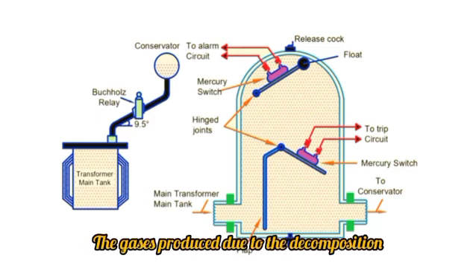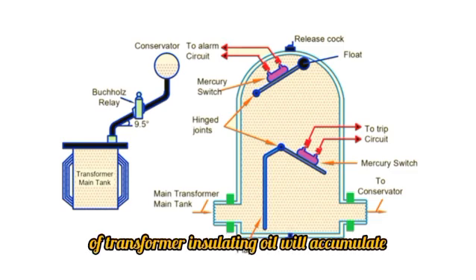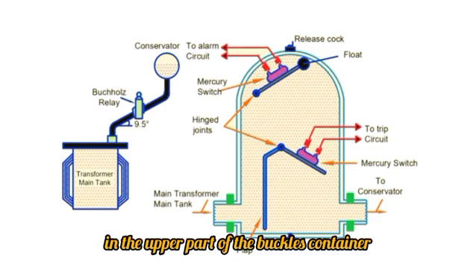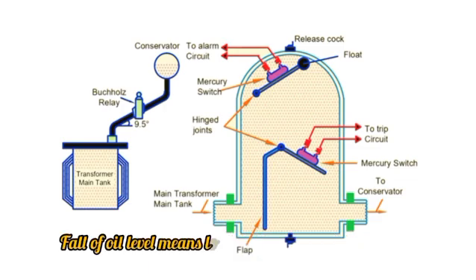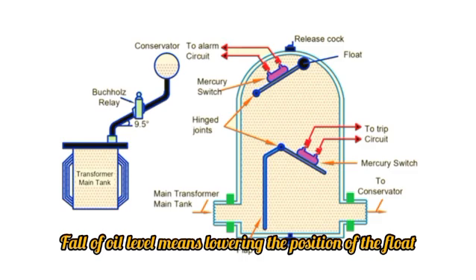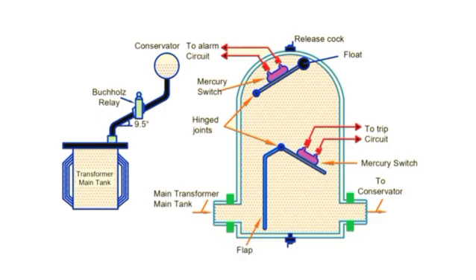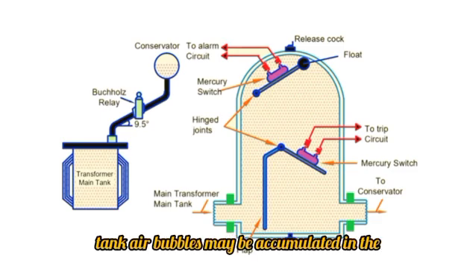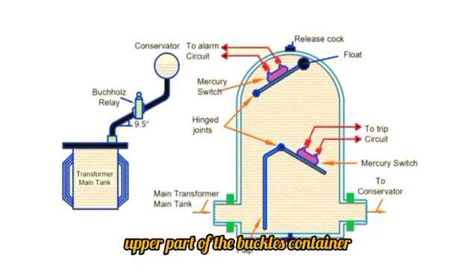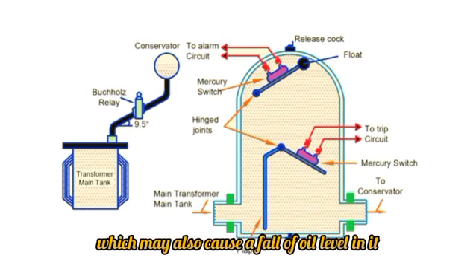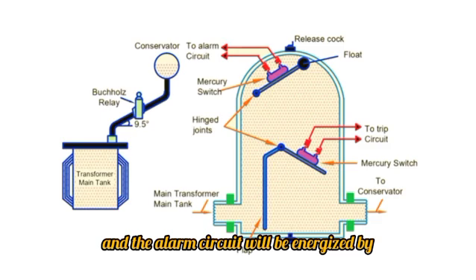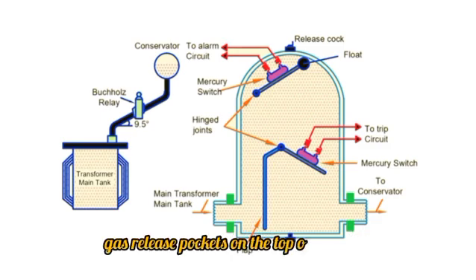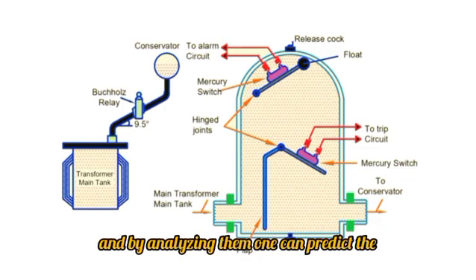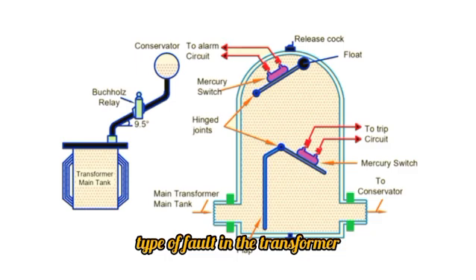The gases produced due to the decomposition of transformer insulating oil will accumulate in the upper part of the Buchholz container, which causes a fall of the oil level in it. Fall of oil level means lowering the position of the float and thereby tilting the mercury switch. The contacts of this mercury switch are closed and an alarm circuit is energized. Sometimes, due to oil leakage on the main tank, air bubbles may accumulate in the upper part of the Buchholz container, which may also cause a fall of oil level in it, and the alarm circuit will be energized. By collecting the accumulated gases from the gas release pockets on the top of the relay, and by analyzing them, one can predict the type of fault in the transformer.